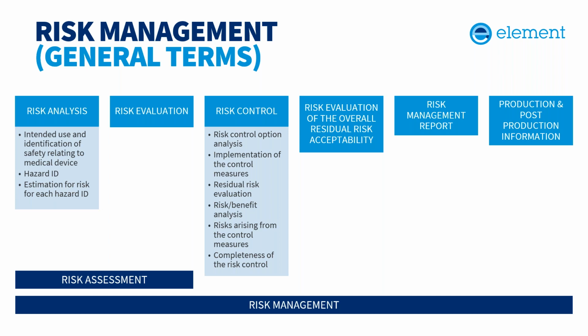So you need to identify critical aspects and sensitive data, build a risk profile for each use case, and determine risks for errors, misuse, software, or firmware problems. You also then need to map how critical portions of the device are linked. For example, if you've got a system that has a half dozen different components in it, you need to look at risks for each of those individual components, how all the different components interact with the whole, and then how the whole system is intended to operate. So you've really got 3 levels of risk analysis there.